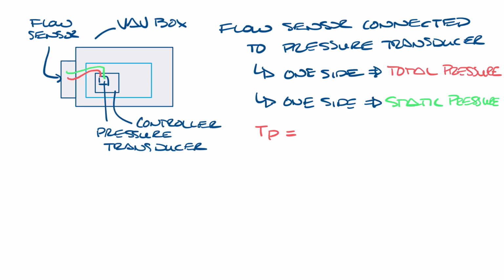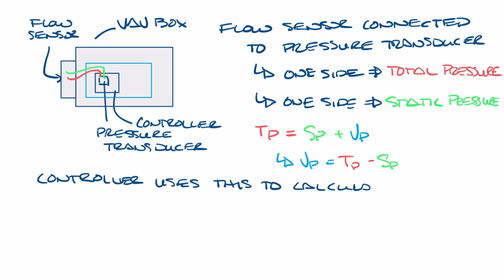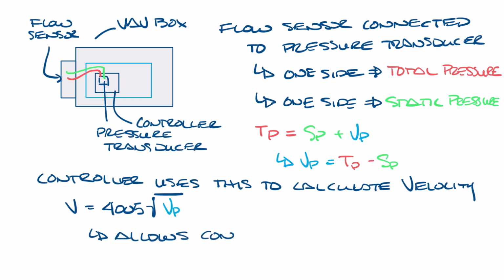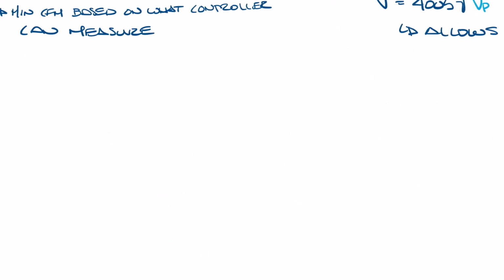If you recall from one of the early videos, total pressure equals static pressure plus velocity pressure. So velocity pressure equals total pressure minus static pressure. So the difference between these two pressures is the velocity pressure of this VAV box at that airflow. The controller uses this to calculate the velocity of the air moving through the box, because velocity equals 4005 times the square root of velocity pressure. And this allows the controller to calculate CFM, because CFM equals velocity times area. Let's move this over again.